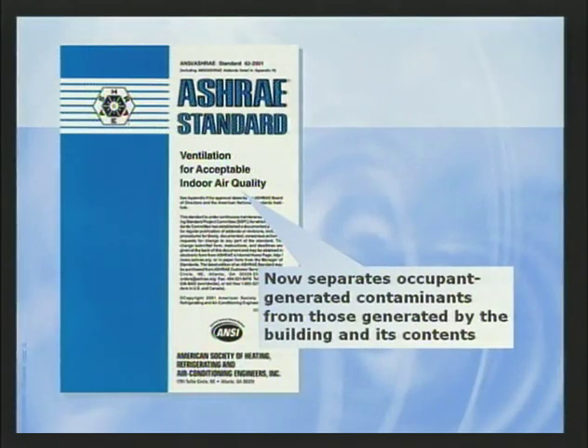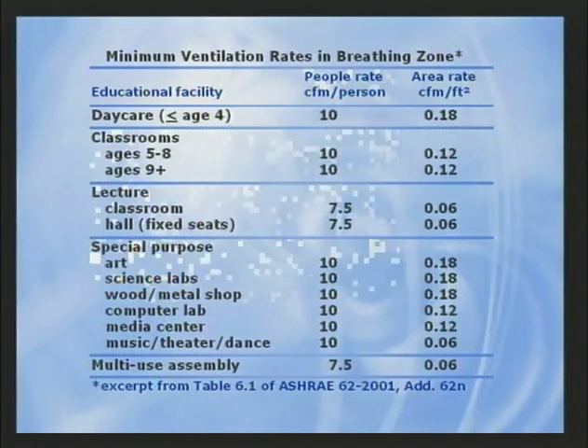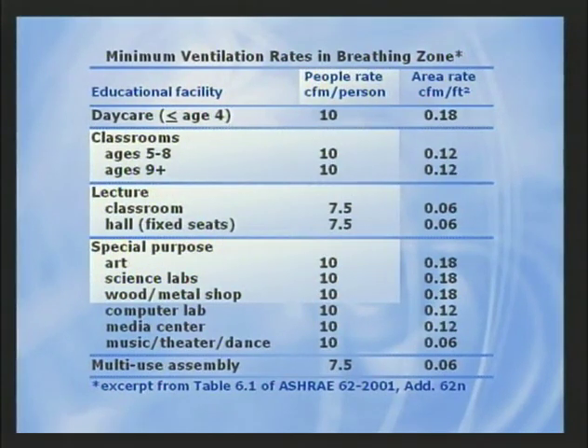Perhaps the biggest difference is that the procedure now separately accounts for the contaminants generated by the occupants and those generated by the building. Here's an excerpt from Table 6.1 of 62N dealing with educational facilities. This table replaces Table 2 in the previous standard. First, notice that some new space types have been added. Some, such as classrooms, have been further broken down according to the age of the students that are expected to occupy them. We can see for both categories of classroom, the amount of outdoor air required for the people is 10 CFM. To that, however, must be added the 0.12 CFM for each square foot of classroom for the contaminants generated by the building and the contents.